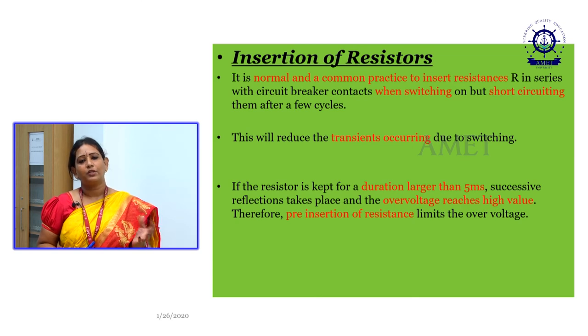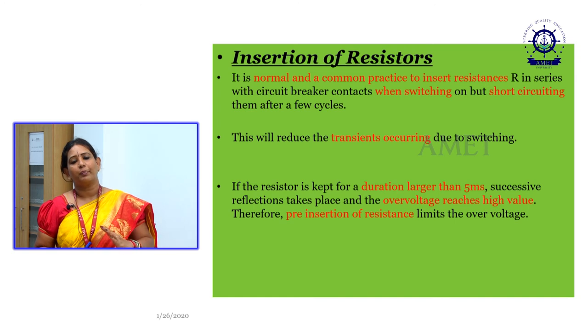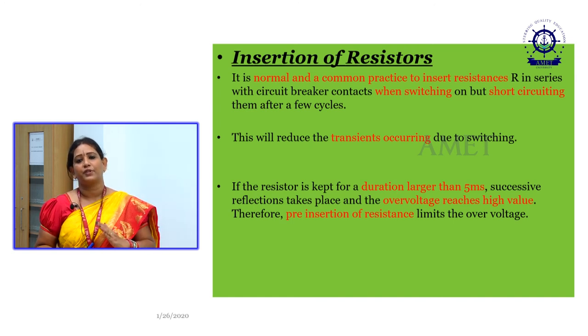Suppose I am adding X resistance and now I am closing it. This is called resistance switching of the circuit breaker. When we switch on the system, the sudden overvoltage which is initiated into the system is nullified, and this resistor will act as a blockage to the sudden increase in overvoltage.